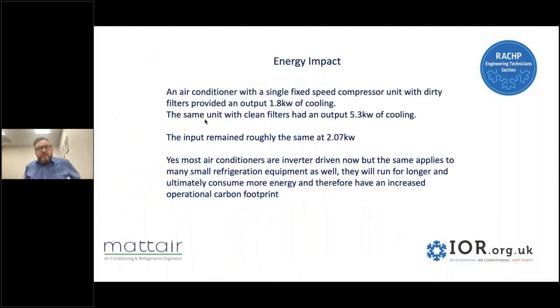Another report that we brought out looked at an air conditioning unit with a single fixed speed compressor and dirty filters, and it only provided an output of 1.8 kilowatts of cooling. The same unit with clean filters had an output of 5.3, and the input remained roughly the same at 2.07. Yes, most air conditioners are inverter driven now, but the same principle applies to small refrigeration systems as well. Inverter, small refrigeration equipment will run for longer and ultimately consume more energy and have an increased carbon footprint as a side effect of that.